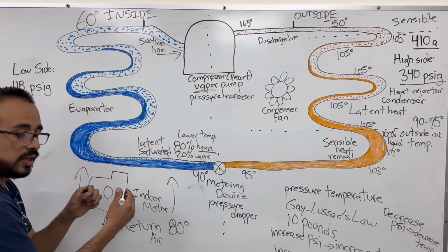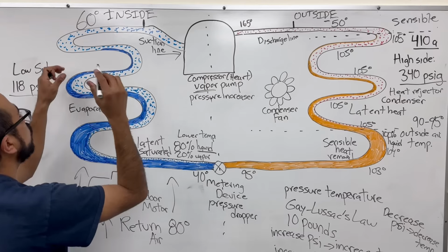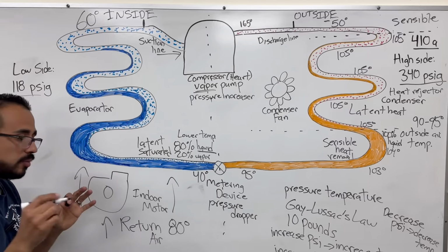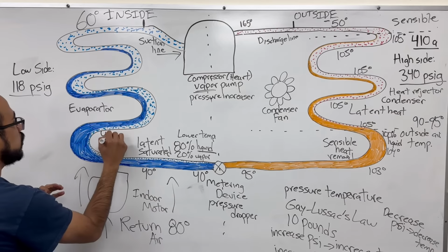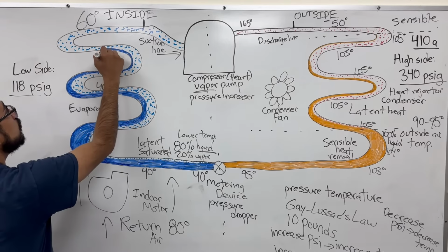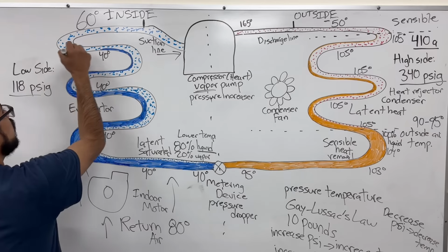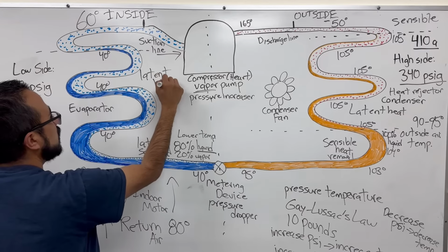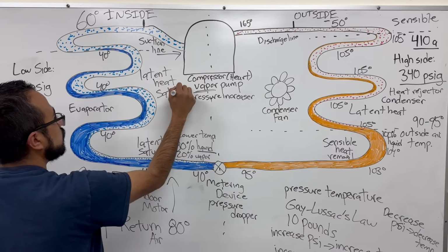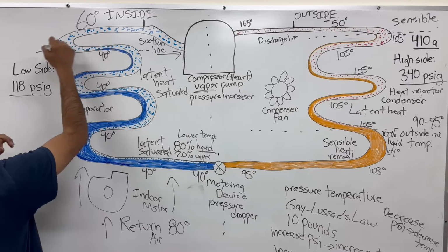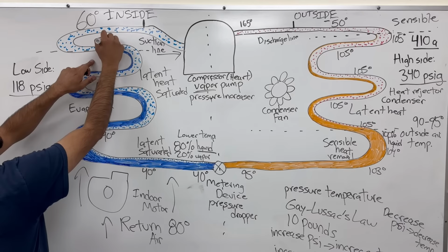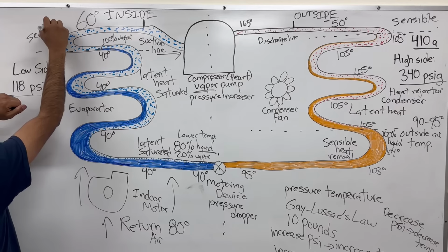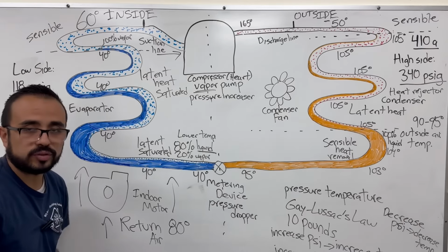It's 40 degrees. And we're boiling off all the liquid until it's 100% vapor. So as long as it's saturated, which we already talked about, 40 degrees, 40 degrees, 40 degrees, last molecule of liquid, 40 degrees. This part here is called latent heat, which we've talked about. Latent heat is saturated. And then this part here, where you have 100% vapor, it is sensible. It is gaining sensible heat. And this is where superheat comes into effect.